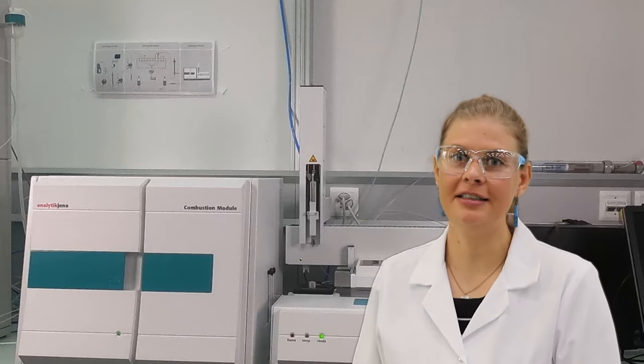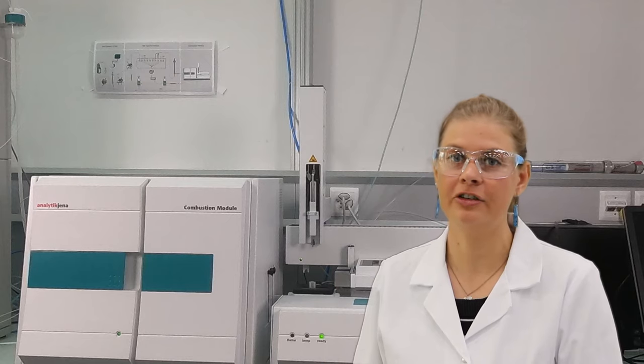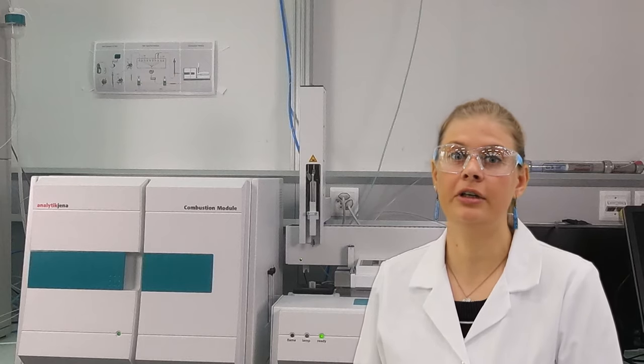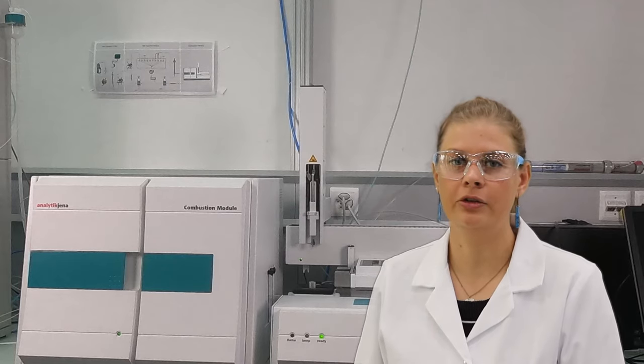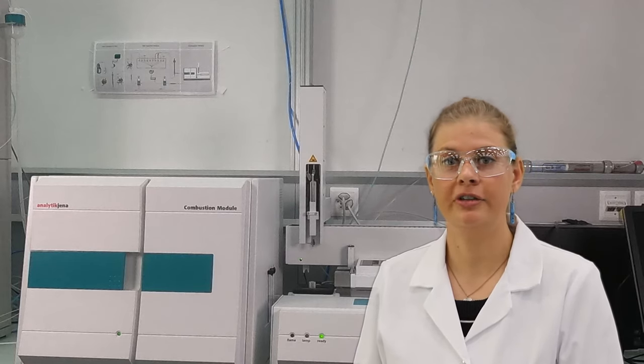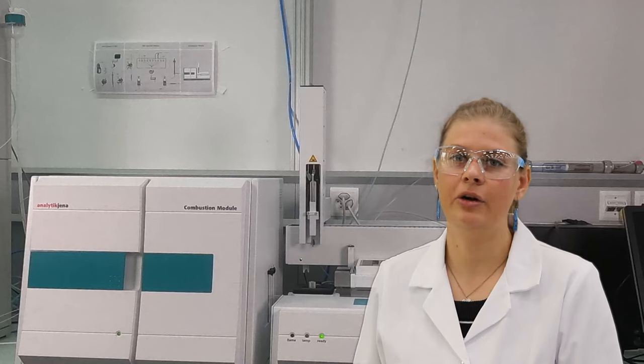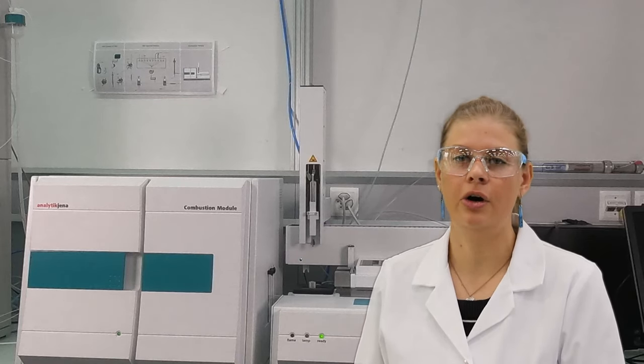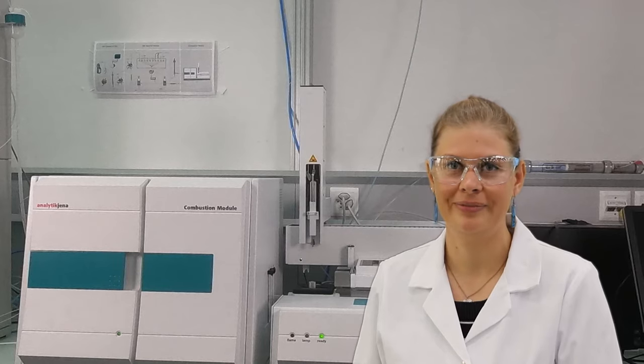The combustion tube of your combustion IC system is essential for the proper functioning of this sample preparation technique. Aggressive samples can attack or even destroy the combustion tube. Also, incomplete combustion of your sample can lead to contamination of the system. These reasons can make the exchange of the combustion tube necessary. Hi, my name is Iris Rieber and in this video I will show you how this is done.